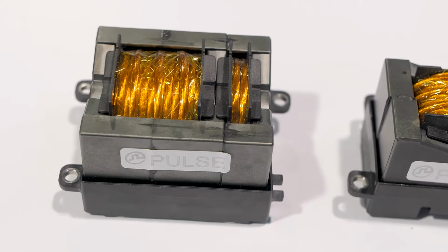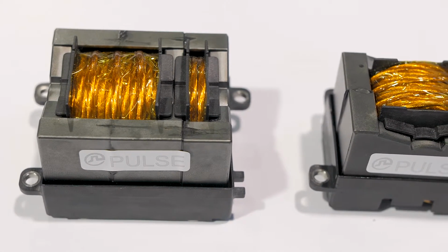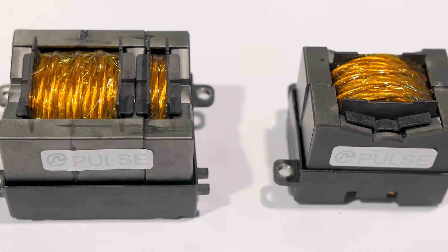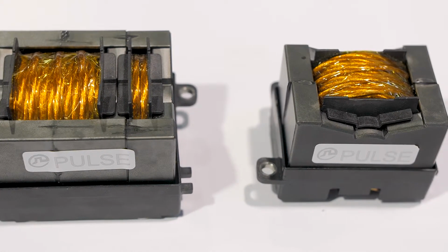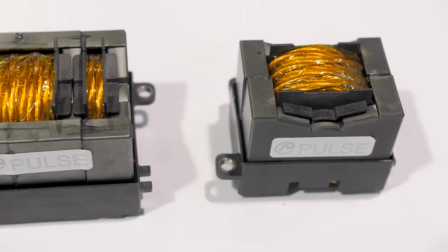Sure. A lot of our customers look at our transformers and think it's kind of like an ideal transformer. So there's just certain turns in the primary, certain turns in the secondary, and you just get this perfect answer. Magnetics in reality don't work that way. So there's a lot of gotchas. There's core losses, AC losses, fringing effects, all sorts of things that affect your efficiency, which affect your thermals.